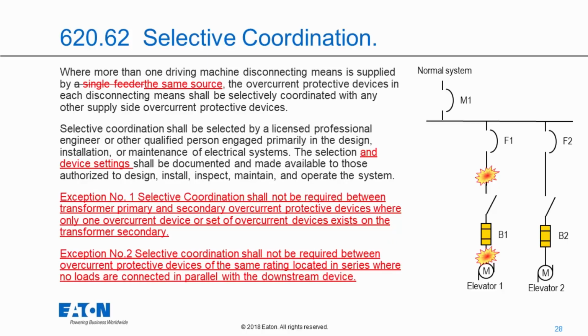So the code only talks about the overcurrent device in B1 and upstream feeders. The question comes, what if the fault is on the load side of F1? If you look at the intent, I think you'd want to analyze the selective coordination of feeder 1 with M1, because we would not want a fault on the load side of F1 such that F1 would open, but it would not open fast enough before M1 would open as well. So this might be outside of what the actual text says, but I think it's certainly a consideration that needs to be done.